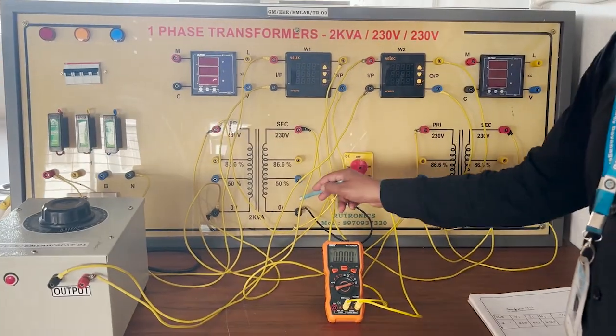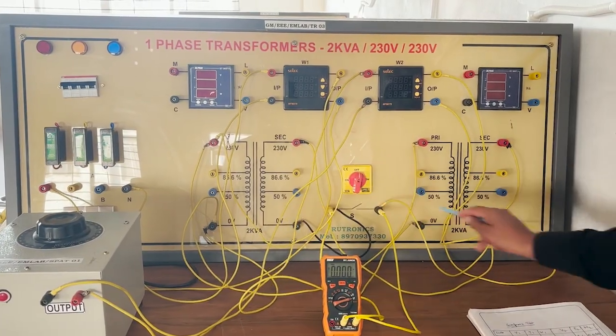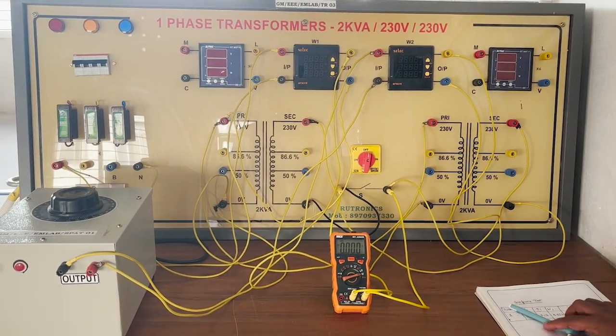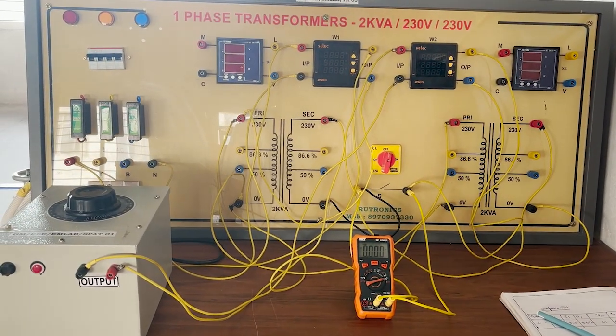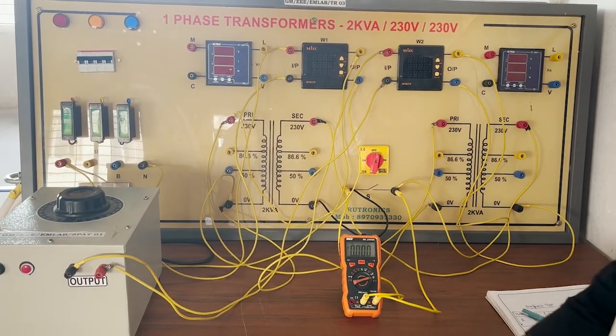So today we are going to study experiment number 2, that is the Sumpner test. The Sumpner test is also called the back-to-back test. In this test we have to determine the efficiency, regulation and power factor of the transformers. This test is conducted by using identical transformers, that is 2 kVA and 2 kVA. Now we have to make the connection as per the given circuit diagram.